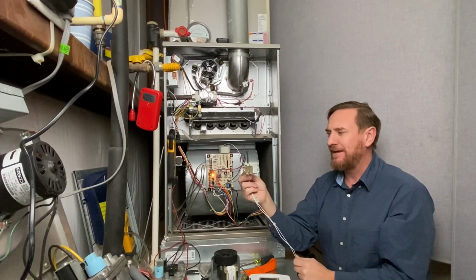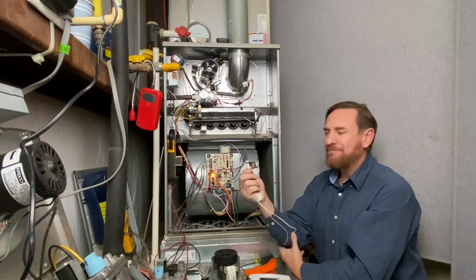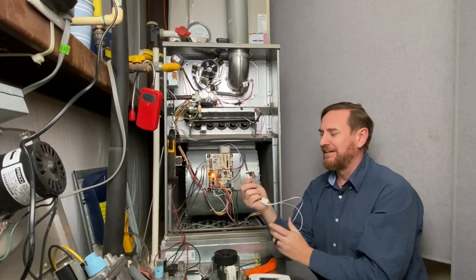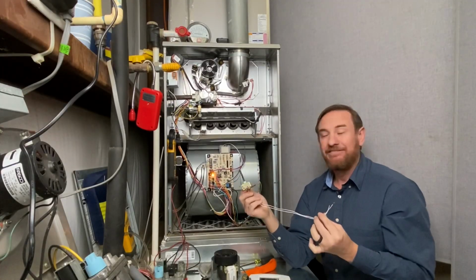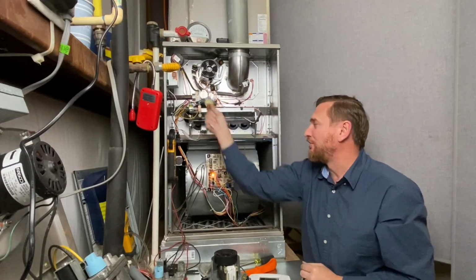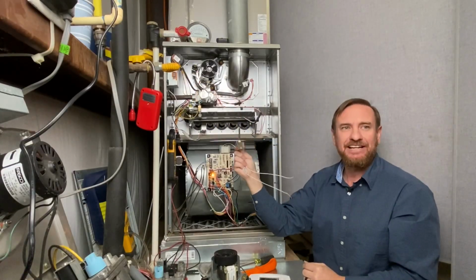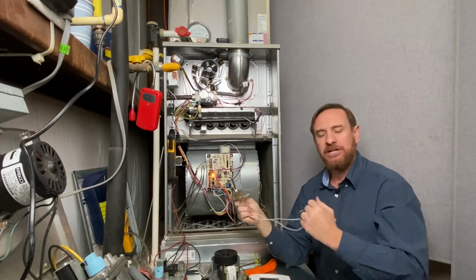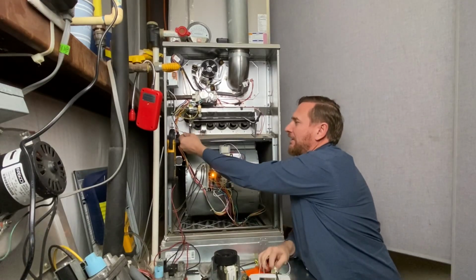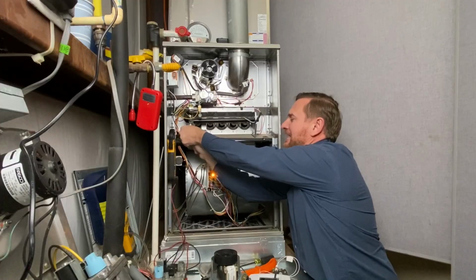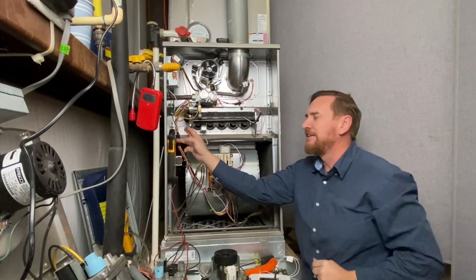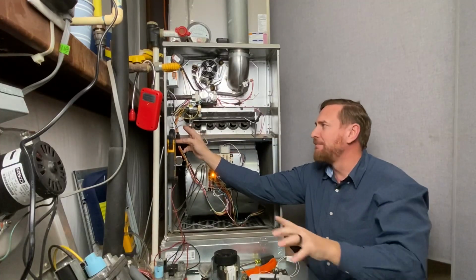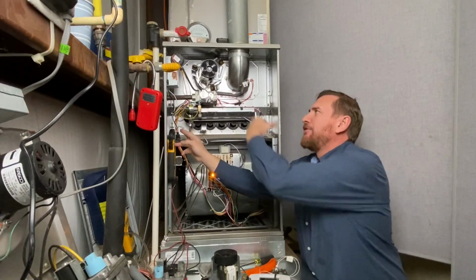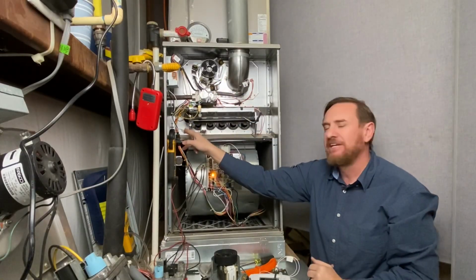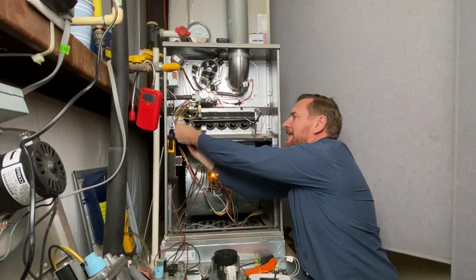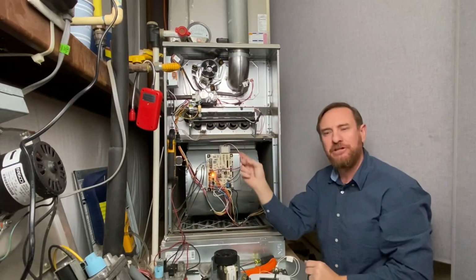They last about 5 years or so, but to see if this is working, if it's getting bright red hot, you know it's probably working. If it's not, well, that's the sequence of operation. Make sure this switch is closing, that switch is closing, this isn't lighting up, let's check this switch. Another way to check it is you can unplug the plug to the hot surface igniter. You can actually check for voltage coming to the igniter in the proper sequence. You've got to remember that it's not going to have voltage all the time. It's got to go through the proper sequence. So if I'm getting voltage here and I plug this back in and the igniter is not getting hot, then we know there's an issue.